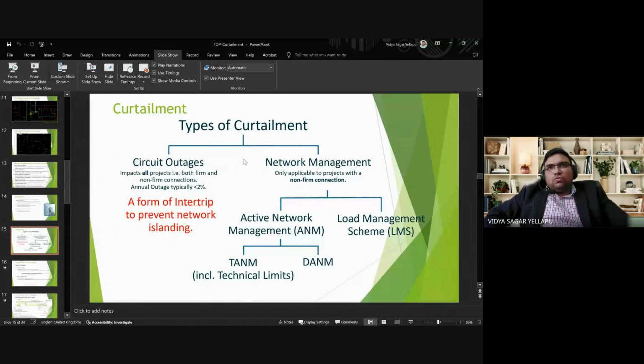There are two types of curtailment. One is because of circuit outages, and the second one is because of network management. If there are key circuits that are needed for the generation to be exported to the wider network, and those circuits go offline, the generators will not have any other path to export their power to the wider network. In that case, 100% of the power of this particular project has to be curtailed, or reduced to zero. That's the meaning of 100% curtailment at that point in time.